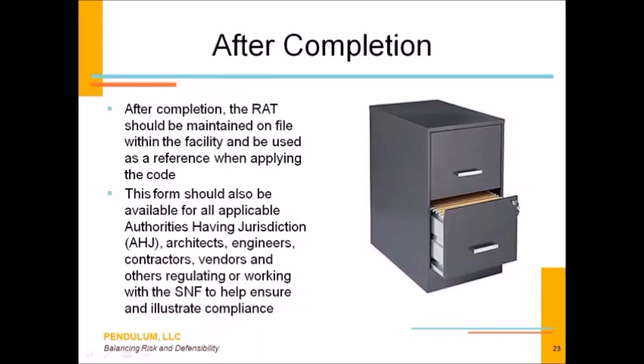Now, there is some very prescriptive information within the code and within the handbook that describes what we mean by serious injury or minor injury. Everybody knows what death means or what discomfort means. So you need to get into the code book, then you need to get in the handbook, and look at all of the information in there describing what those different categories really mean. Once you determine what your risks are after completing an NFPA 99 risk assessment tool, you then are able to determine what elements of the code apply.